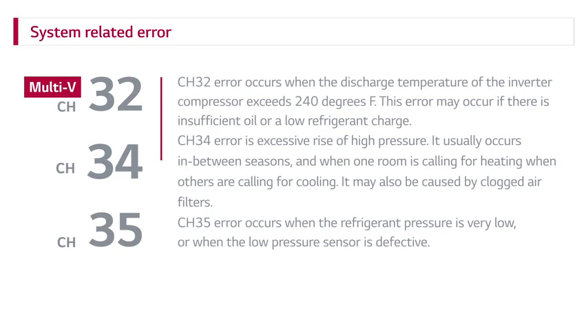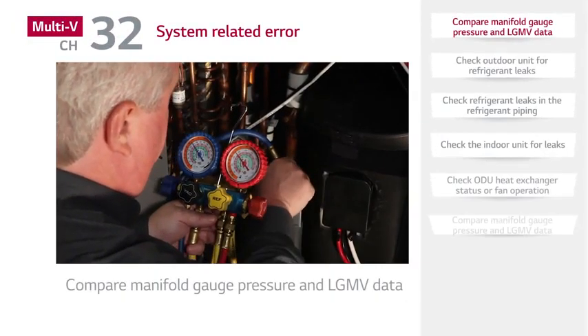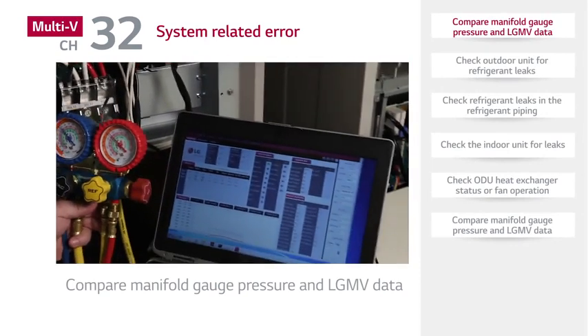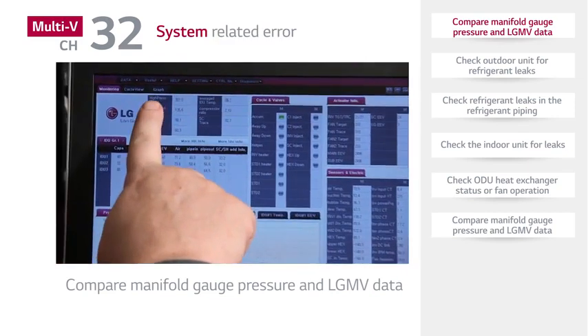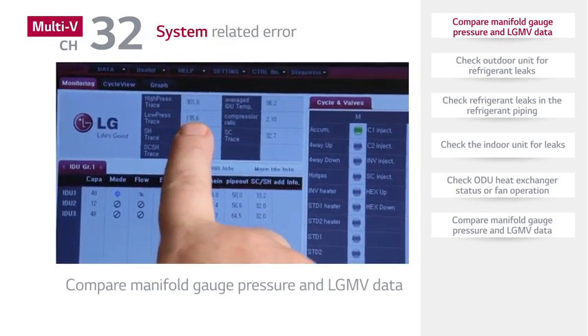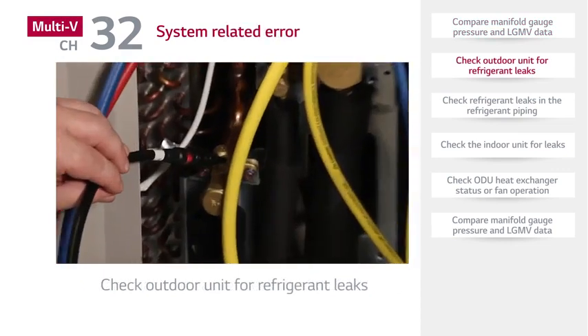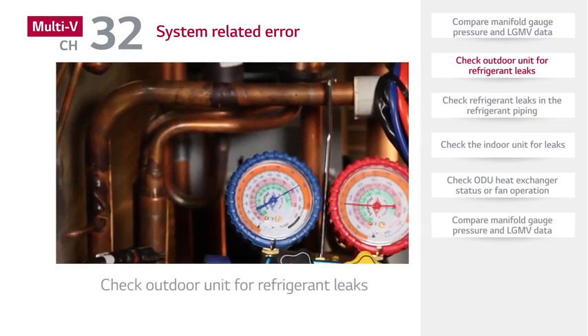CH-35 error is an error that occurs when the refrigerant pressure is very low or when the low pressure sensor is defective. Compare manifold gauge pressure and LGMV data. If there is a problem with the refrigerant pressure, inspect the outdoor unit for refrigerant leaks.